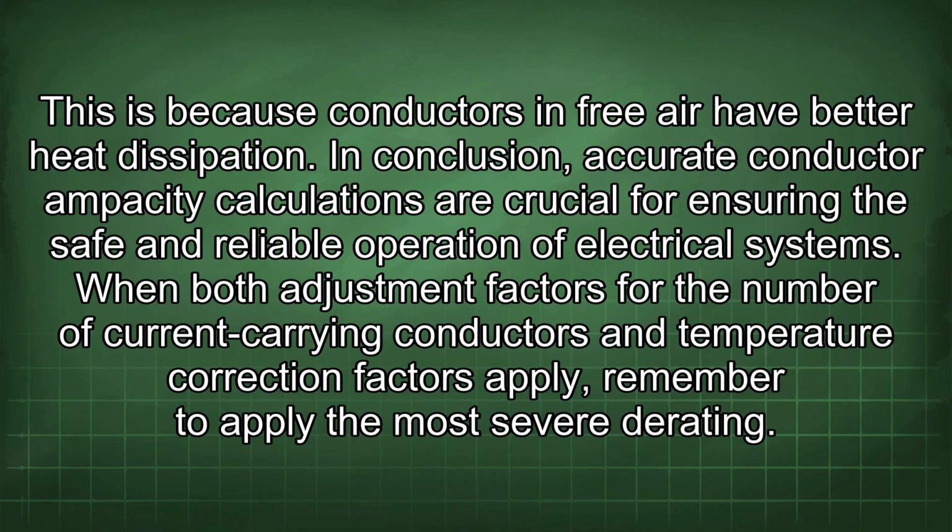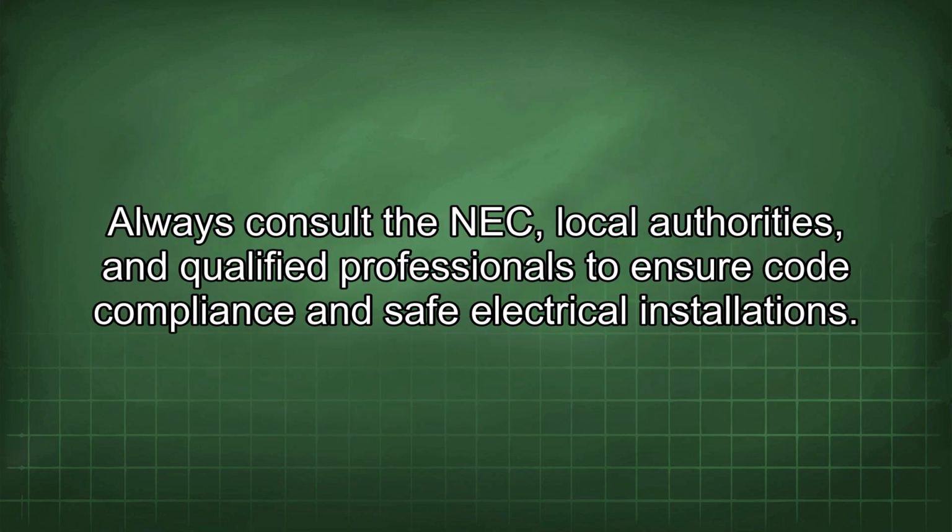In conclusion, accurate conductor ampacity calculations are crucial for ensuring the safe and reliable operation of electrical systems. When both adjustment factors for the number of current carrying conductors and temperature correction factors apply, remember to apply the most severe derating. Always consult the NEC, local authorities, and qualified professionals to ensure code compliance and safe electrical installations.